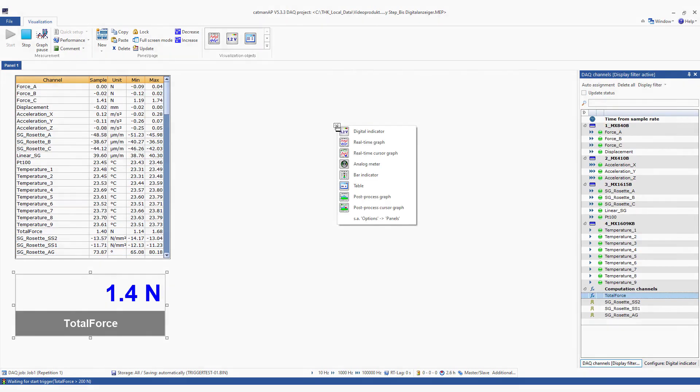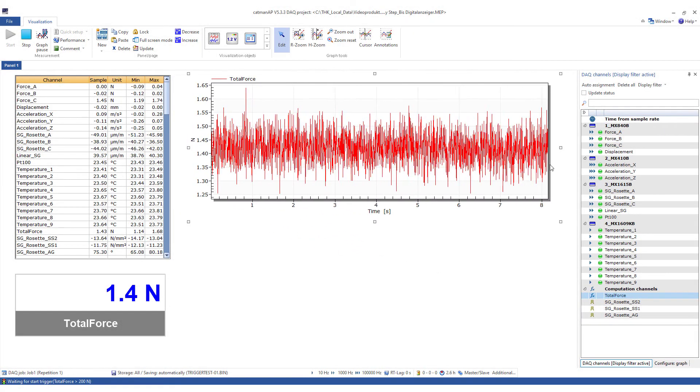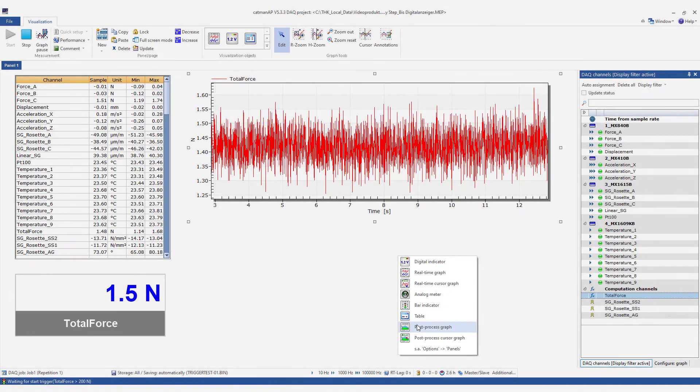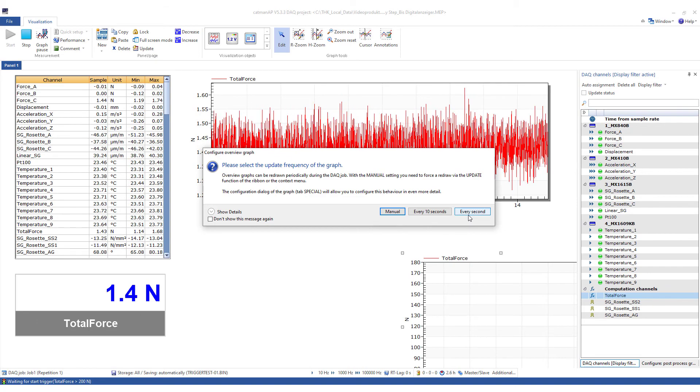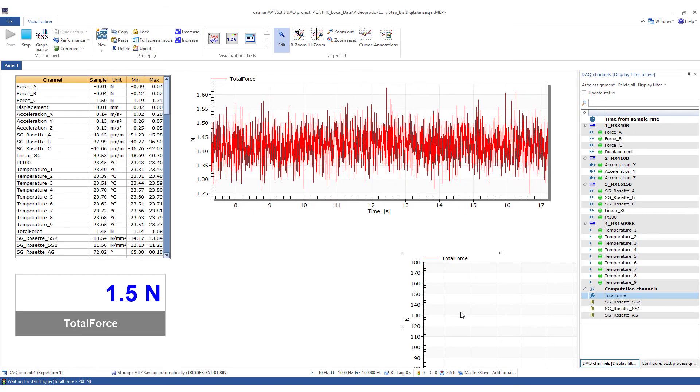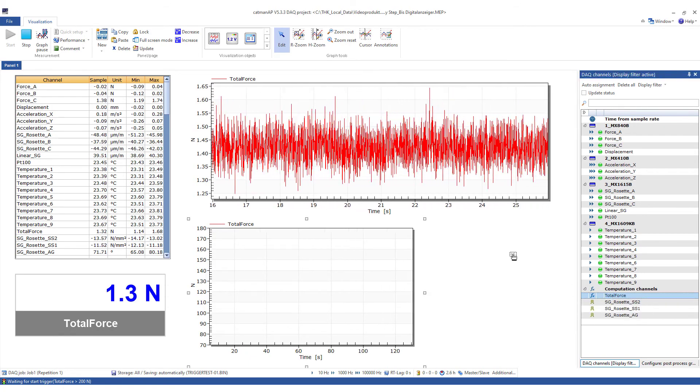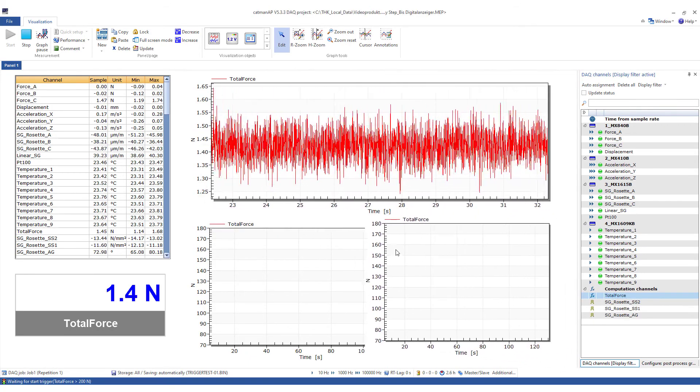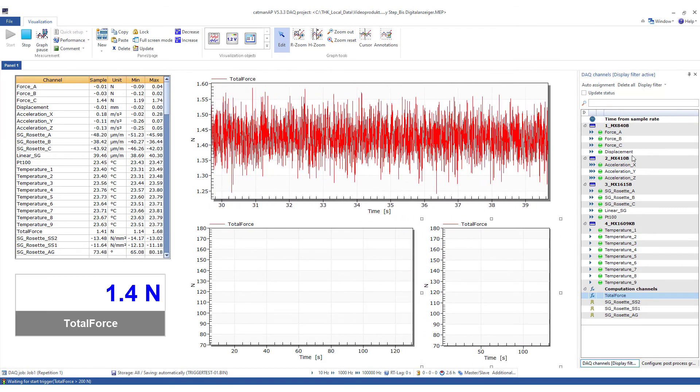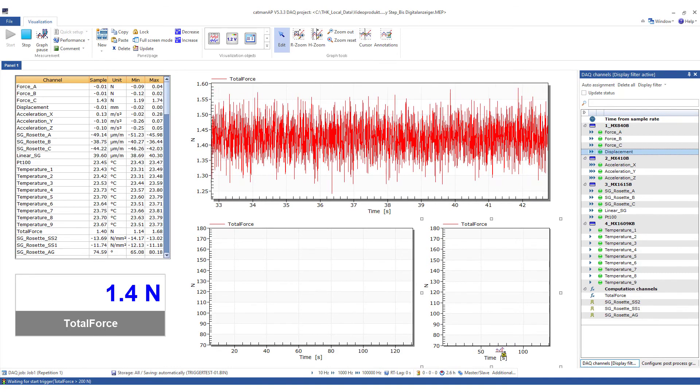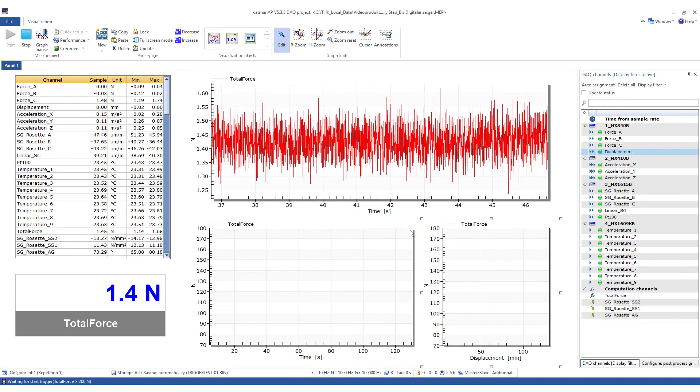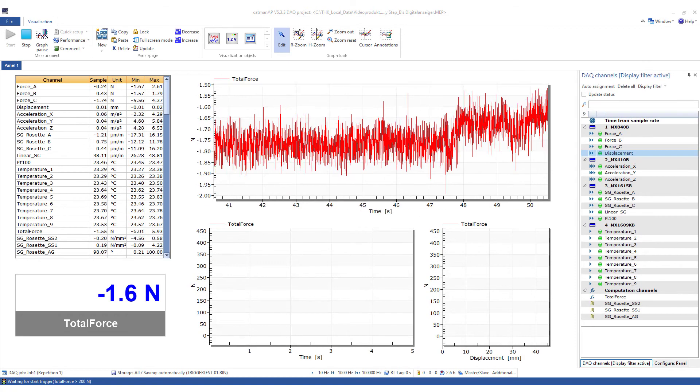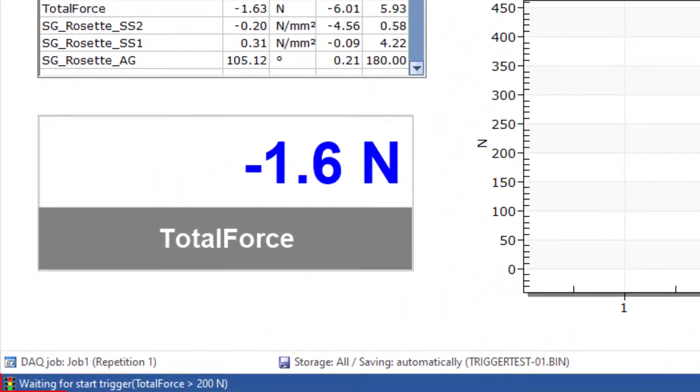And now I'll add a real-time graph, which is also created directly from the channel. Now, I'll create an overview graphic of the total force. Of course, the measured values are displayed versus time. Catman asks how often the display shall be refreshed. Every second is exactly right here. In this graphic, I want to show the total force versus the displacement. To do this, I'll simply drag the displacement channel onto the x-axis. The overview graphs currently do not display any measured values because no measured values have been saved yet since the trigger condition has not yet been fulfilled. I can see that below.